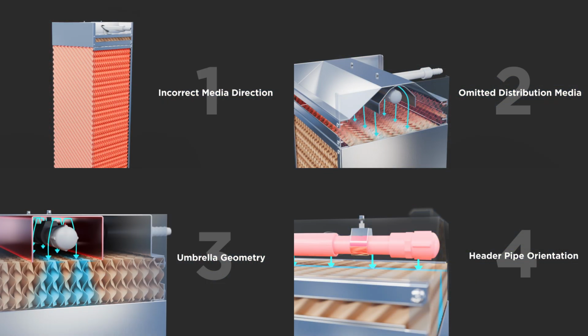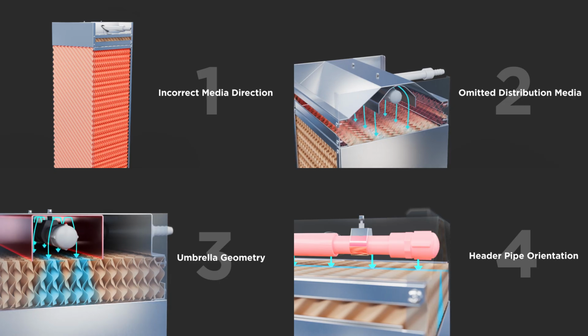Evaporative cooling relies on proper water distribution in the media for effective cooling. Incorrect configurations can lead to issues, reduced efficiency, and an increased potential for carryover. Here are a few scenarios and their solutions.